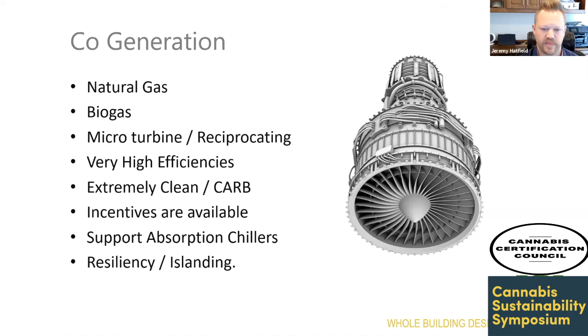I did a real simple exercise here. We took that same load profile, the blue line, and created all of our electricity from natural gas micro turbines, then plotted the cost on that same summer day—we're down to $1,000, so we saved about $100 on that day. That's calculated using, in this particular location, 5 cents a kilowatt hour for natural gas, and a price from a micro turbine supplier of 7.5 cents a kilowatt hour to lease it.